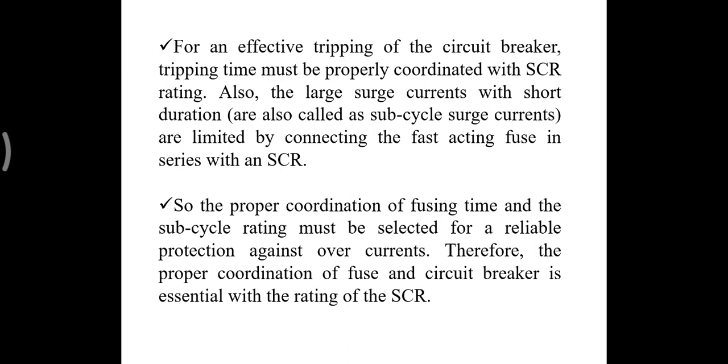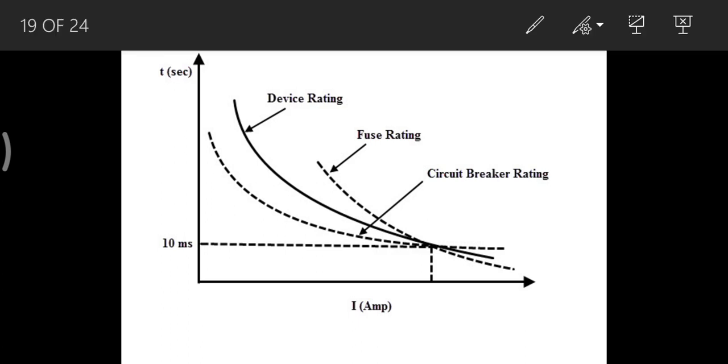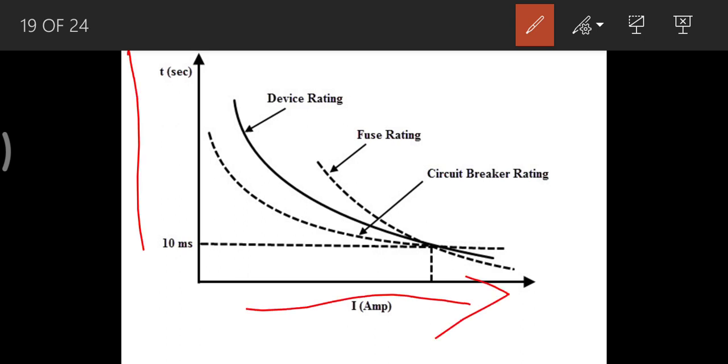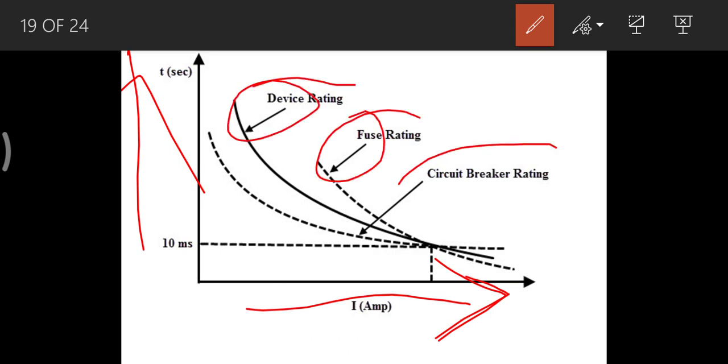So proper coordination of the fuse time and subcycle rating must be selected for reliable protection against overcurrents. We have to choose the proper rating of the fuse to protect the SCR. See here, this is the time, this is the current, this is the time, this is the device rating, this is the fuse rating, this is the circuit rating.